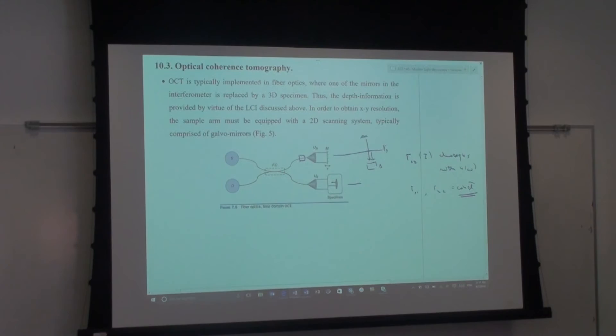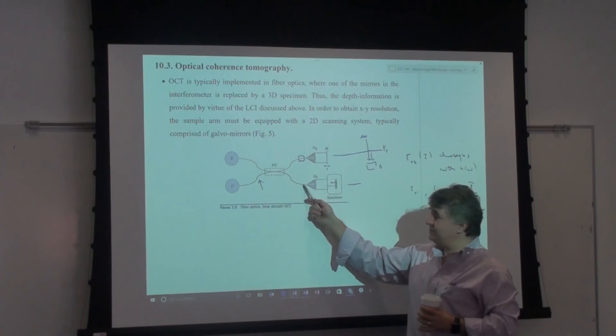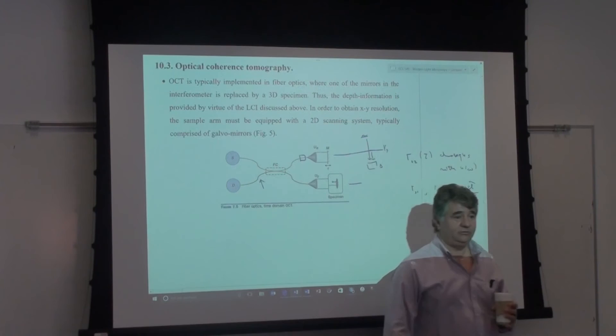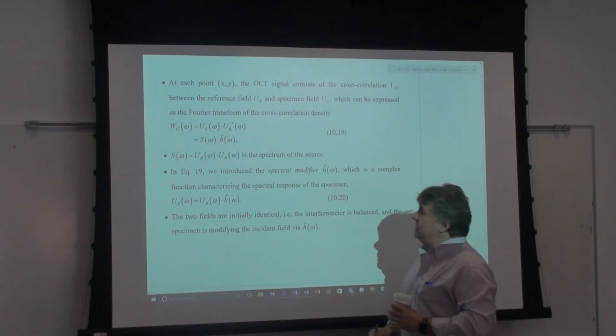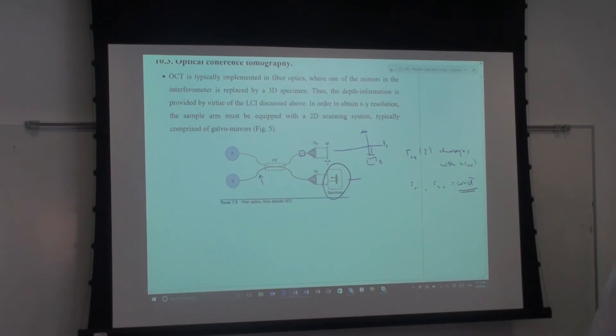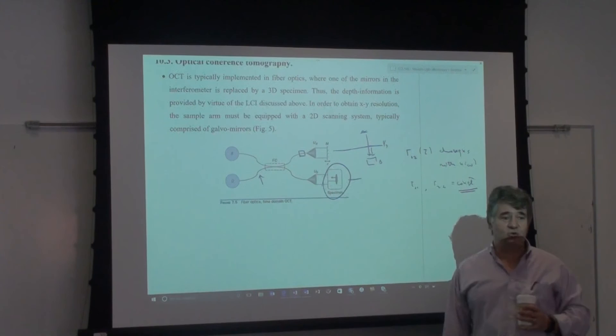OCT systems are typically fiber-optic based, which contributed to early success: all components — fiber couplers (50/50 beam splitters), fiber collimators, mirrors — were readily available as off-the-shelf telecom components at 1.3 μm or 1.5 μm wavelengths. You can assemble a basic interferometer in an afternoon. For imaging, the mirror on the sample arm is replaced with the object — for example, the eye — to perform depth imaging.